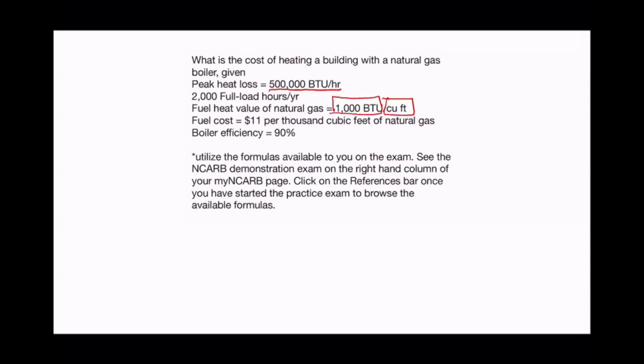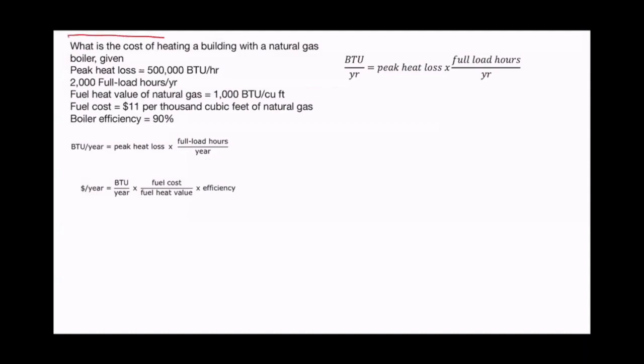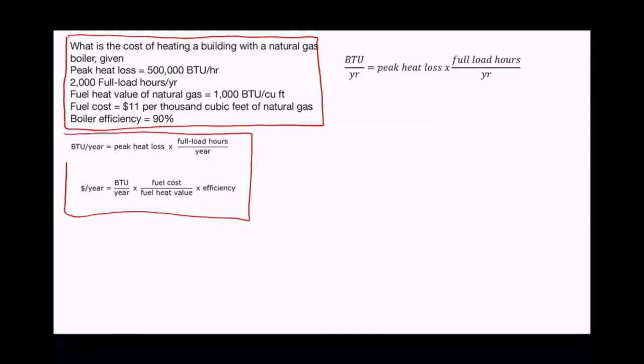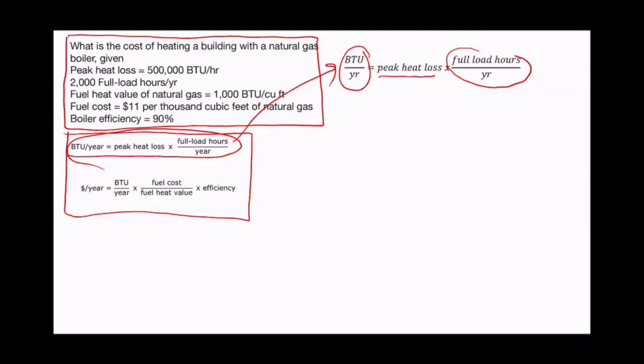All right, so we'll take what we were given in the problem, and we'll put it up here in the corner for your reference, and we'll take what we found on the exam, given to us as part of the formulas, and we'll put it right there. And we'll pull out this one right here, and we'll bring it over here, and we'll start to figure it out. So BTUs per year, that's what we're trying to figure out, how much heat per year. And that's going to be equal to the peak heat loss times the full load hours per year. Now, as always, don't just look at that as an abstract set of formulas that you can plug in.